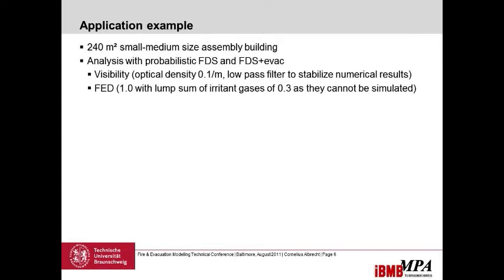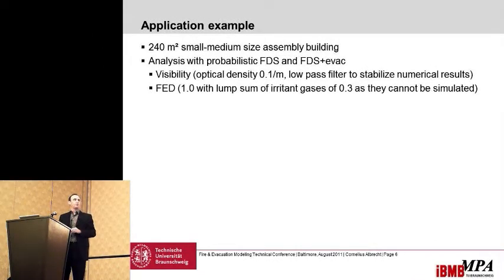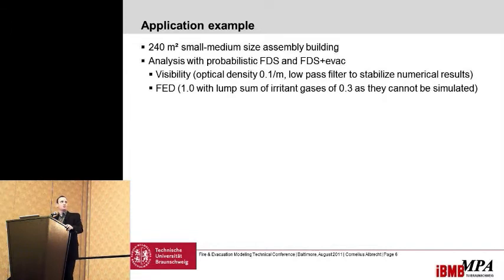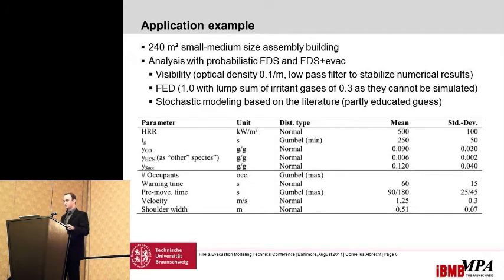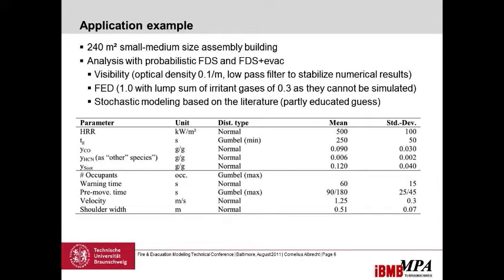The probabilistic CFD analysis used the Fire Dynamics Simulator for CFD and FDS+EVAC for evacuation. The threshold for visibility is an optical density of 0.1 per meter, and I applied a low-pass filter to stabilize the numerical results because they were very unstable — the results from FDS go up and down, possibly due to numerical issues. I also used a fractional effective dose threshold of 1.0, with a lump sum of 0.3 for irritant gases included because we can't currently simulate them. The stochastic modeling is partly literature-based and partly an educated guess, since data is absolutely missing — something we need to work on.